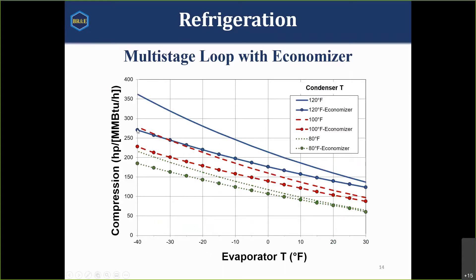The economizer is really beneficial when there's a large temperature difference between the condenser and evaporator. At a 120-degree condenser temperature, the economizer drops power requirements from about 360 down to about 230–270 horsepower — roughly a 25 percent reduction. The difference diminishes as the condenser temperature goes down or as the evaporator temperature gets closer to the condenser temperature.